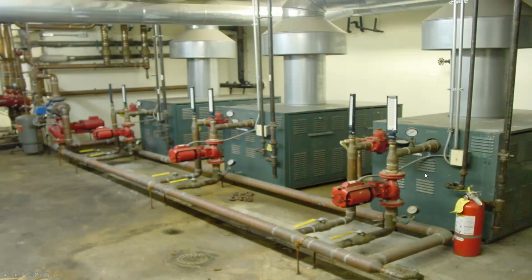And then you have to have the return come back over here. That moves over. That moves over. Now you've got your two pipe manifolds, supply and return. They're not seeing each other. That goes away. Yes, that would be a real quick fix.